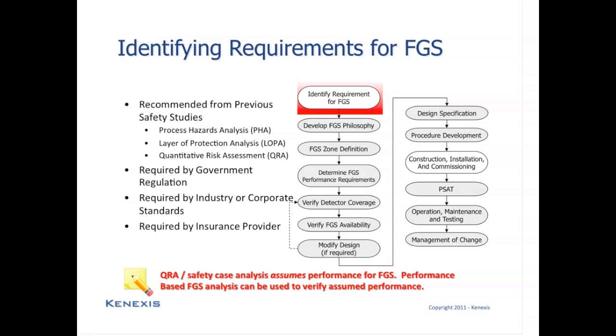Also, other more detailed risk analysis techniques such as layer of protection analysis often recommend that fire and gas system designs be considered. And finally, a lot of jurisdictions require the use of quantitative risk assessment studies as part of the licensing or the license to operate phase of a process design. And in a lot of cases, a quantitative risk assessment study may actually assume that a fire and gas system is in place and is in operation when they analyze their risks.